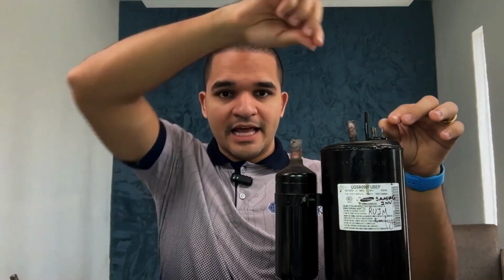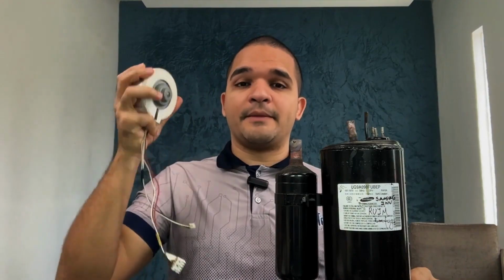What are you going to check at the condenser? The first thing is to check the compressor. Disconnect it from the system, do the same procedure, turn the system on. The relay clicked now, but it didn't shut off. The compressor is shorted. Did it trip again? Then you're going to remove the fan, whether it's from the evaporator or the condenser, okay?